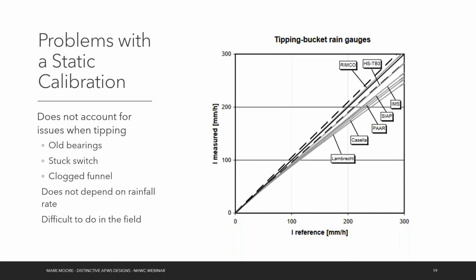And this is a little graphic I found from a study that was kind of showing different tipping buckets and how accurate they are at different rainfall rates. And once you start hitting 200 millimeters of rainfall an hour, you start to fall pretty far behind that 1-to-1 line. You would hope that the measured and the reference at 200 millimeters per hour of rainfall are the same. But you can see most tipping buckets actually start to fall below that 1-to-1 ratio because of the fact that they lose rain as they're tipping during high rainfall rates. Again, that's more of a tipping bucket talk than a calibration talk, but something to be aware of.